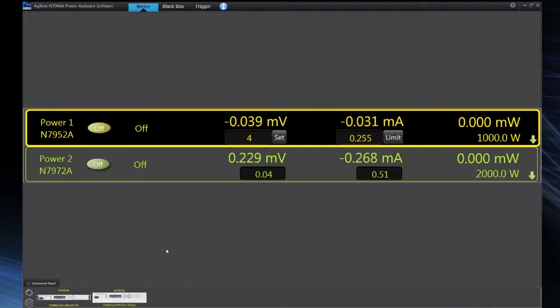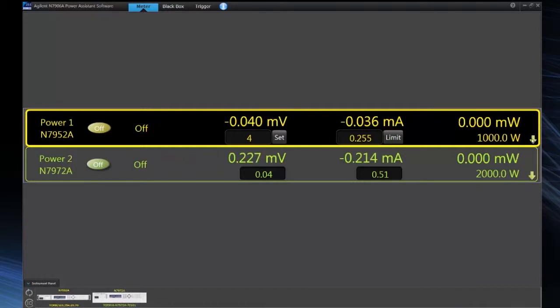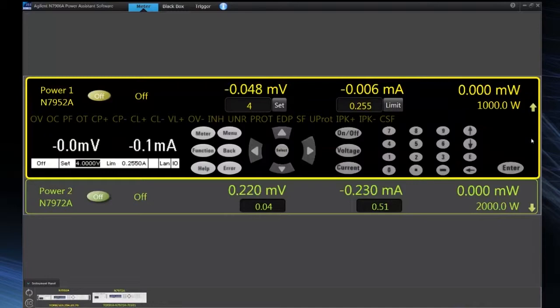So if we look at our meter and control view, we can see the output voltage and current measurements for power supply one and power supply two. If I expand the view for the one kilowatt power supply, we access a lot more information.